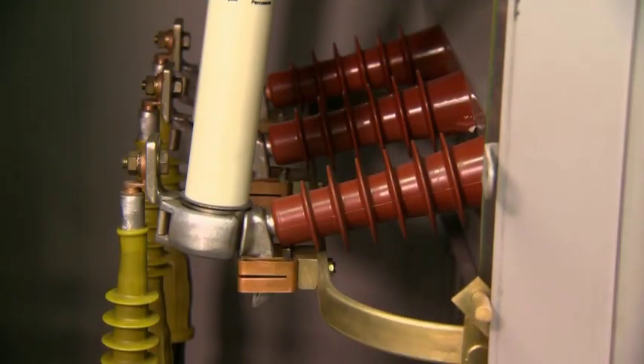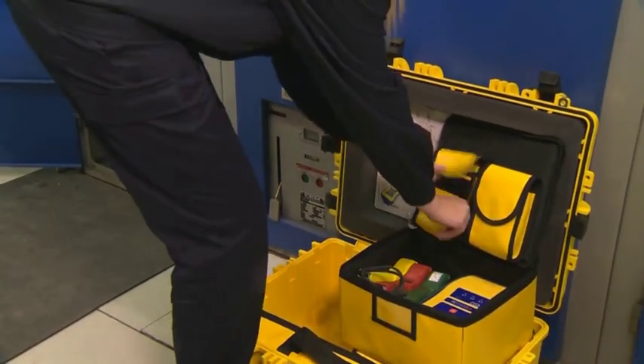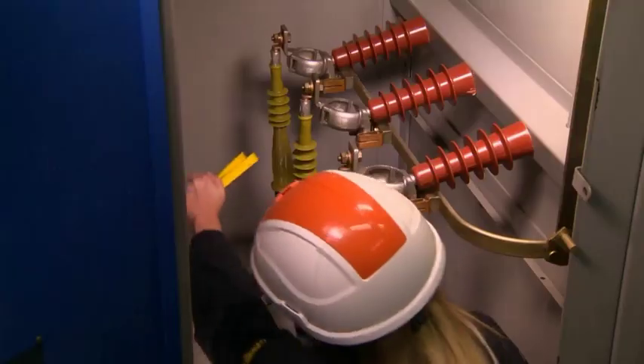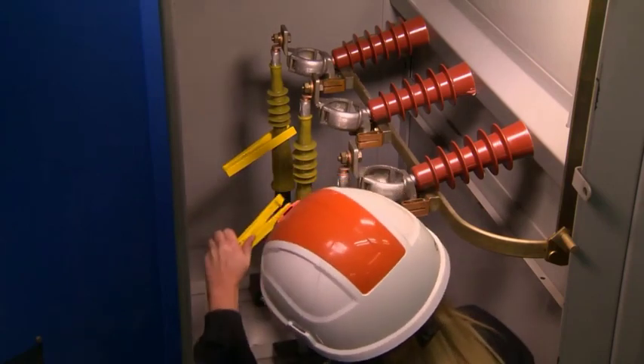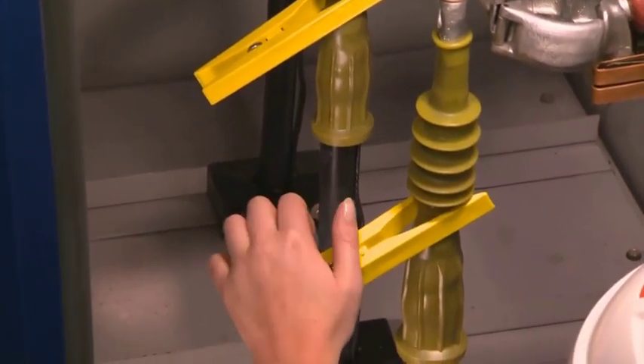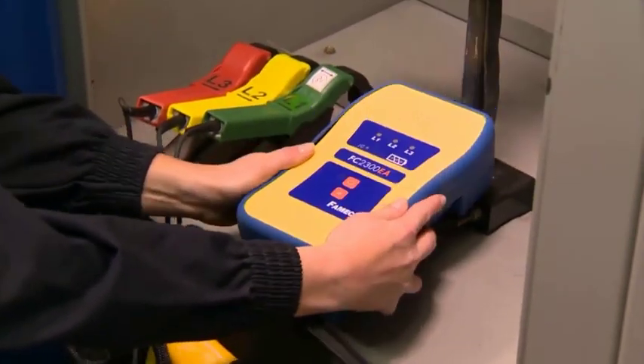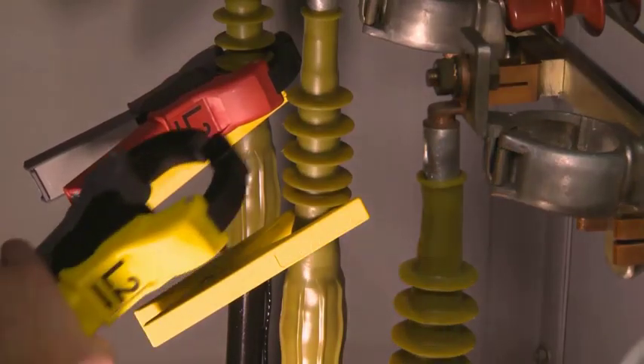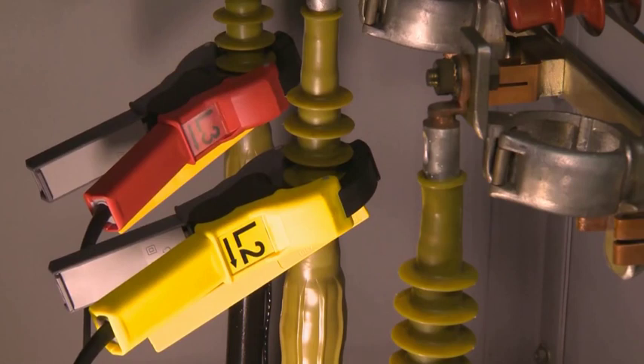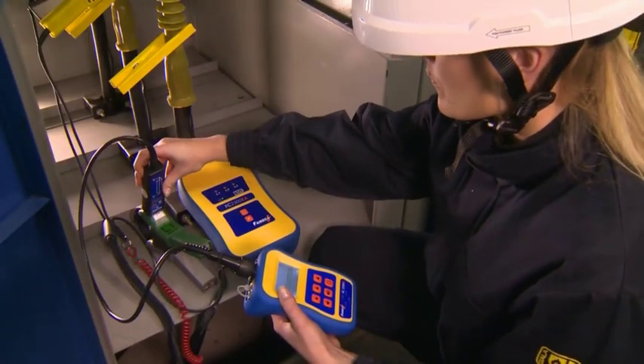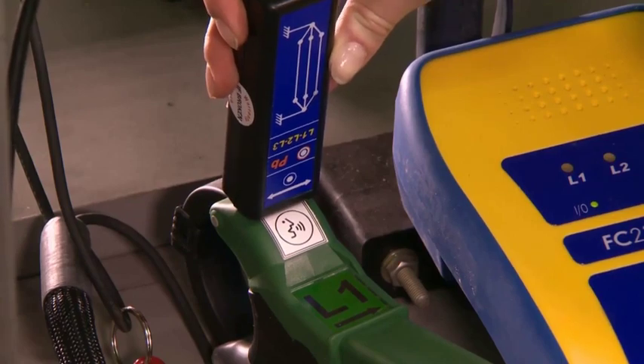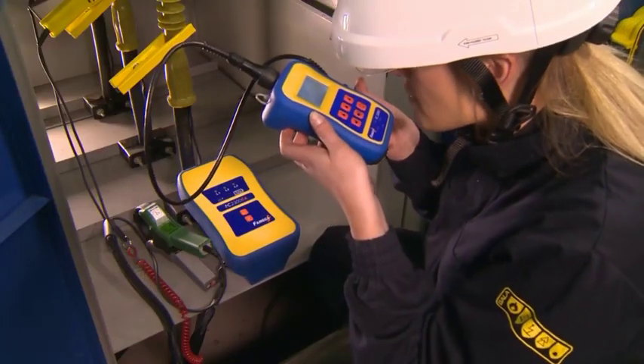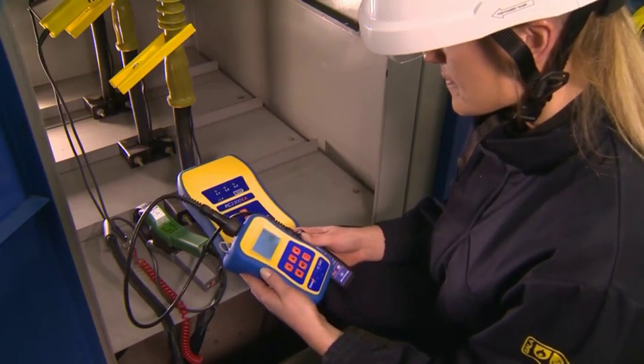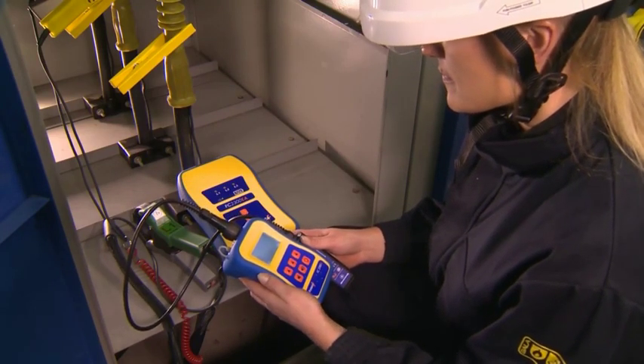In fact, the operators wanted a means of identifying cables compatible with safety procedures. Removing grounding means additional back and forth and messages at each stage of the operation, and thus more risks. Here is the step-by-step procedure developed by Famica. You must position all the three clamps in the same direction and avoid crossed circuitry. The yellow clamps help to guarantee the right position. In order to provide additional safety features, identification signals can be personalized. A voice message can be recorded with each transmitter in a completely secured way.